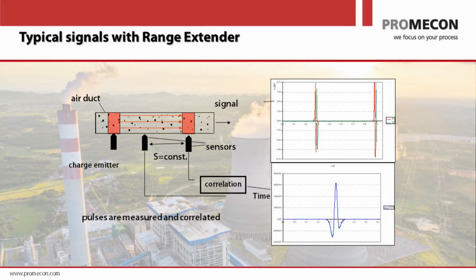Now, again, many people believe that if they don't see the measurement being noisy, but it's more continuous and more following nicely, that the measurement is accurate. But that's not the case. Especially thermal mass flow anemometers appear to be very smooth in transmission, but especially at the high end, they can be awfully wrong, because at the high end, they don't measure very well. They measure the low end very well. So here in our measurement, it's completely opposite. We have a digital flow, it's linear, and at the high end and the low end has the same accuracy. It will not degrade in accuracy.